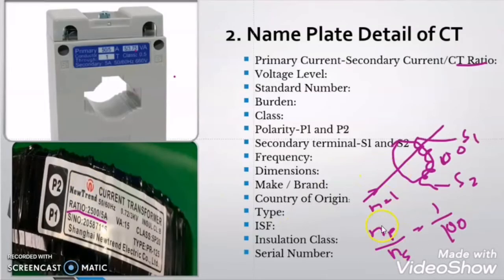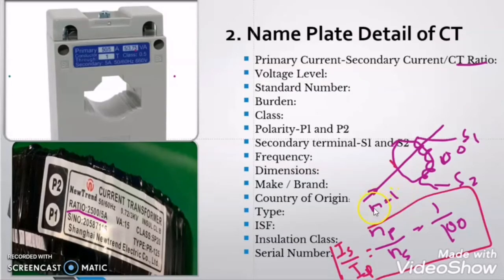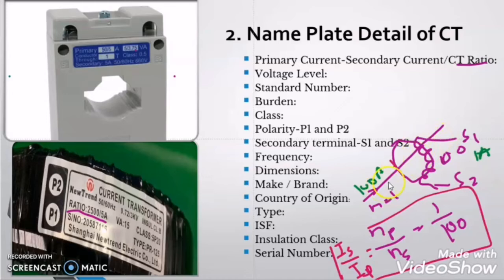So what we derive here is that the number of turns in the primary winding is only 1 conductor and the number of turns in the secondary winding of the current transformer is 100. So NP by NS is equal to 1 by 100, and we can say that NP by NS is equal to IS divided by IP. From here we can conclude that when there is 100 Ampere of current flowing through the primary winding — that is the single conductor — then there will be 1 Ampere of current in the secondary winding. This CT is stepping down the primary current 100 times in its secondary winding.